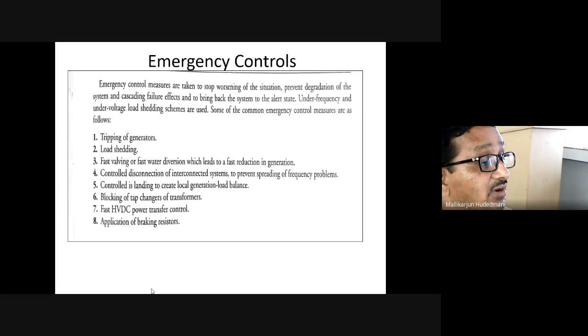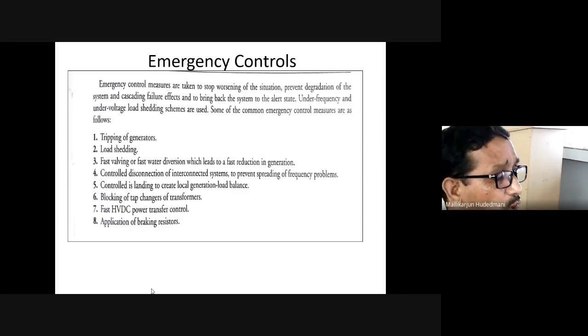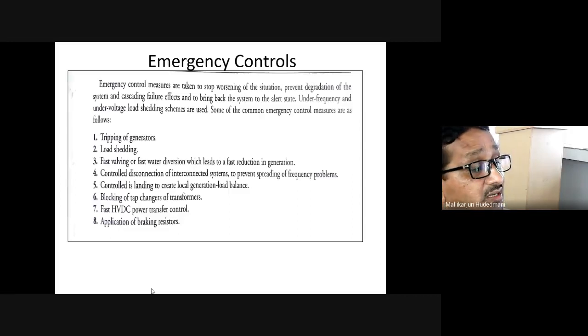That situation can be avoided, situational effects can be minimized, and further degradation and cascaded failure prevented, which can bring the system back to a controllable state wherein it can be brought coolly back to normal. Under frequency, under voltage, load shedding, etc. are the common emergency controls which we have here.